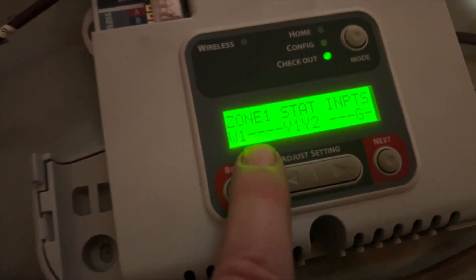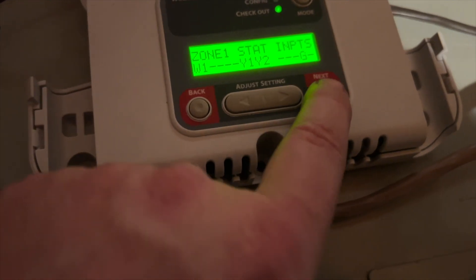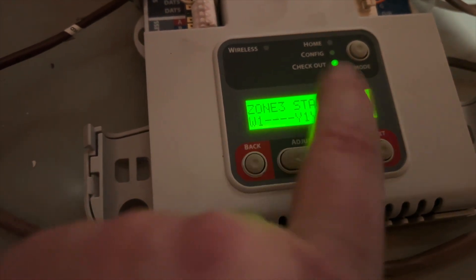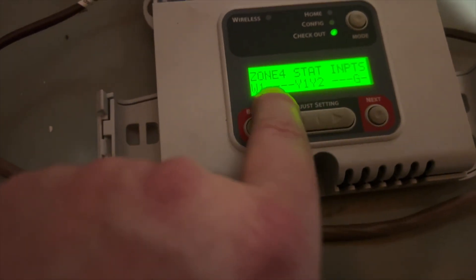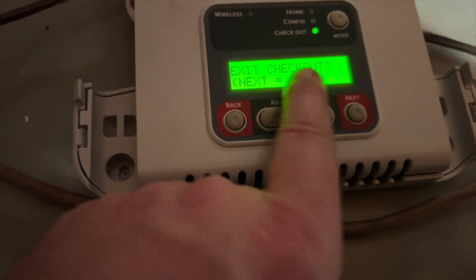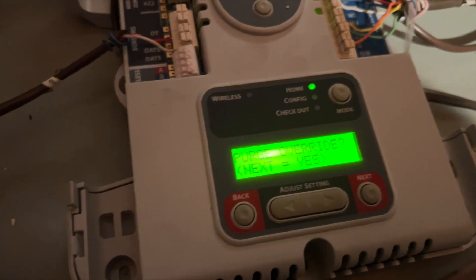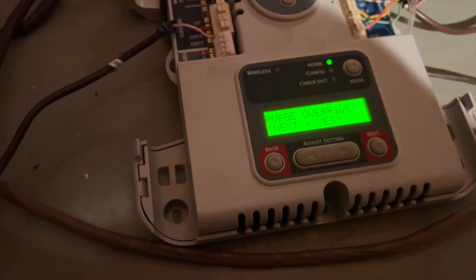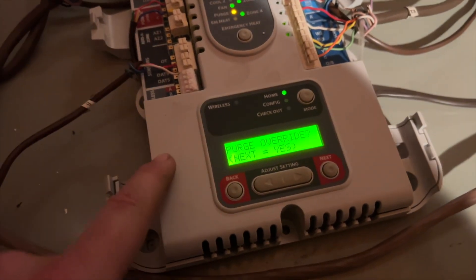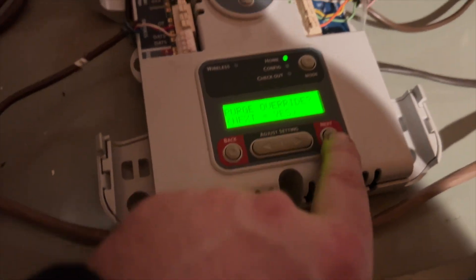So that's really powerful when you're testing. Here you can see what the thermostats are calling for. So zone one right now is calling for W1, Y1, and G. Zone two, same thing. Zone three, it's not calling for fan, just for heat pump and auxiliary heat. And we're asking for fan, heat pump, and auxiliary heat. And then if we hit next, we can exit it. So that's going to do this little thing and go back to home mode. And then it's going to purge, and then once we hit next to override the purge, or if the purge finishes, it's going to go ahead and go back into whatever the thermostats are asking for. So we'll hit next. There you go. So thermostats for all four zones are asking for heat one, heat two, and fan.